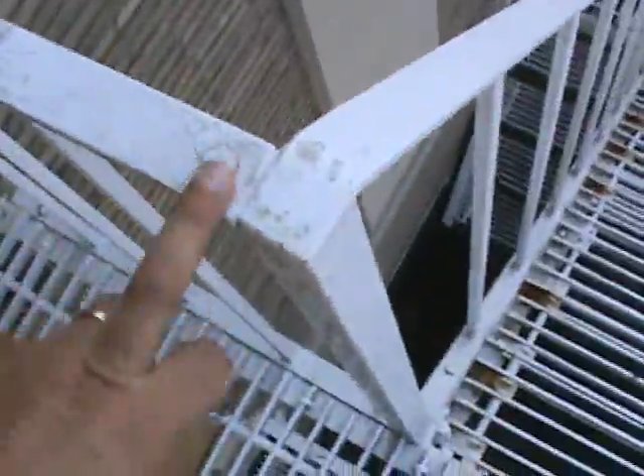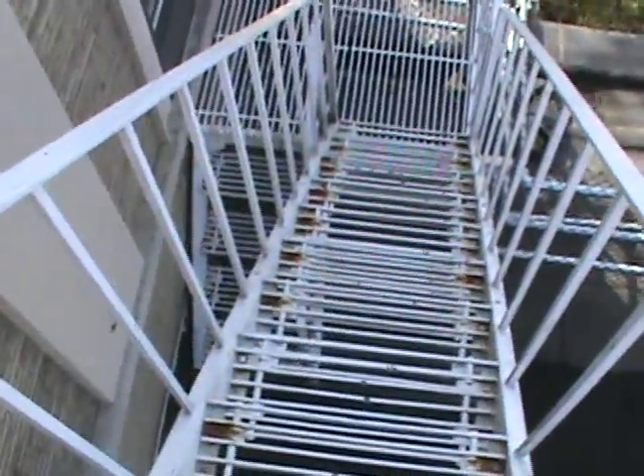In the bolts, you see original hardware and you see changed-out hardware. So you see square heads and hex heads. It's got more paint than rust, believe it or not. So a spot paint will make this pass and get it another 5 years before they have to do something. And then we're going to talk about the grading.